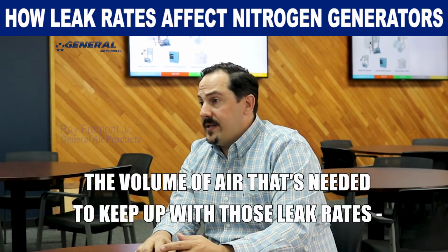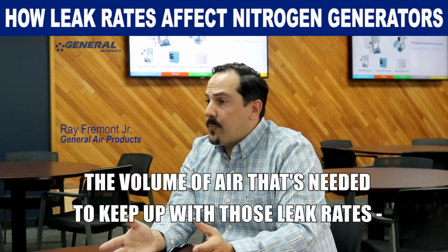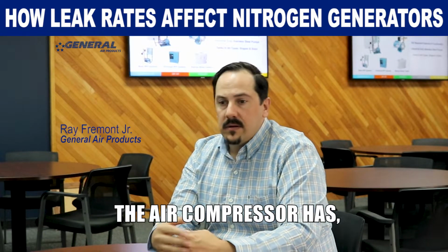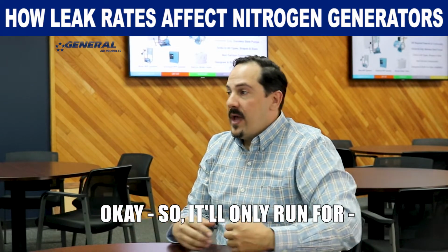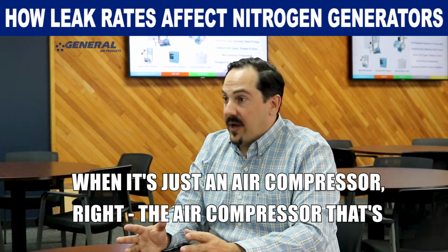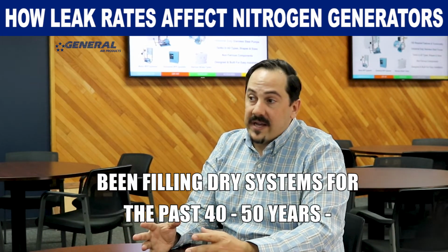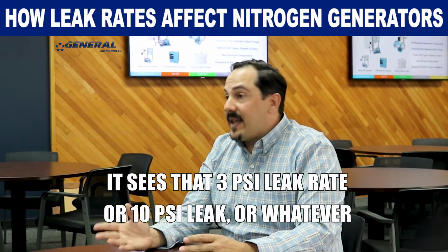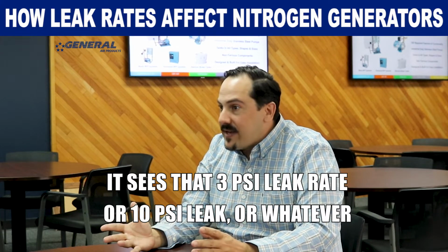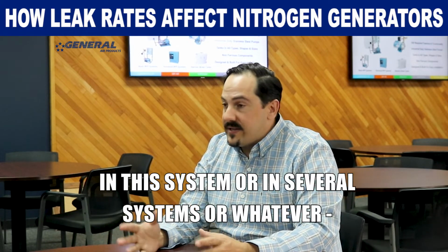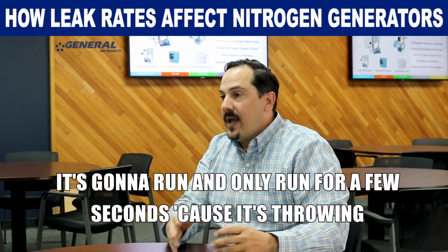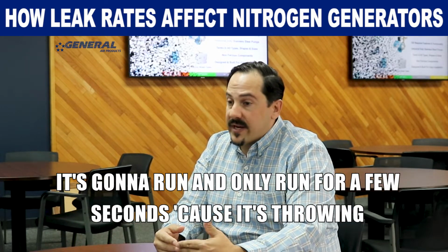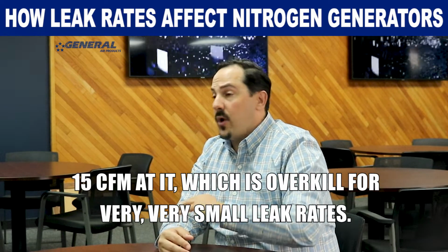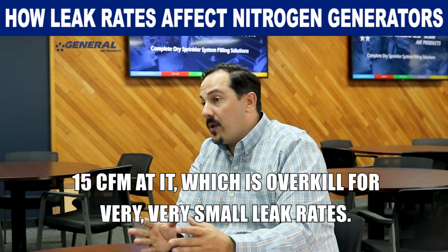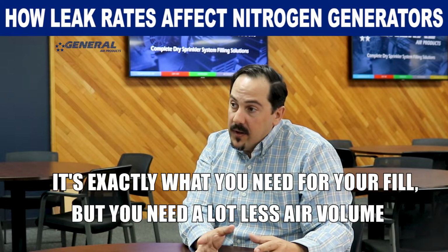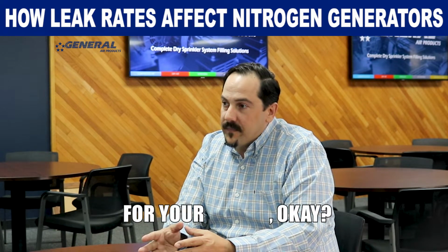The volume of air that's needed to keep up with those leak rates, the air compressor has in abundance. It'll only run when it's just an air compressor, right? The air compressor that's been filling dry systems for the past 40, 50 years sees that 3 psi leak rate or 10 psi leak or whatever in this system or in several systems. It's going to run only for a few seconds because it's throwing 15 CFM at it, which is overkill for very small leak rates. It's exactly what you need for your fill, but you need a lot less air volume for your leaks.